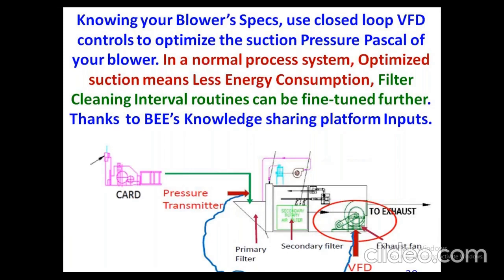If you fix a VFD, the VFD will sense the pressure in Pascal required at the blower header, that is, the waste collection header near the carding machine, and it will maintain the blower at 45 instead of 50 Hertz. It will maintain at 35 Hertz also. Closed loop control for a given centrifugal blower is mandatory. It has to be done. A variable torque load gives 30% savings.